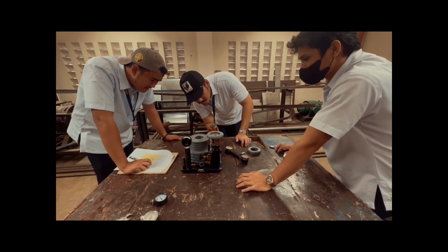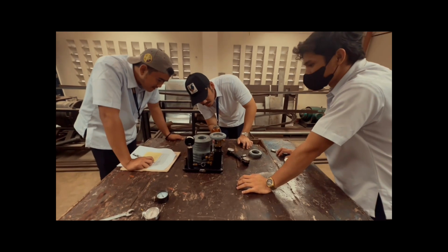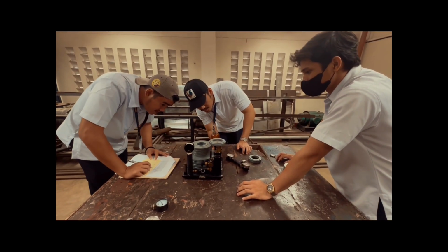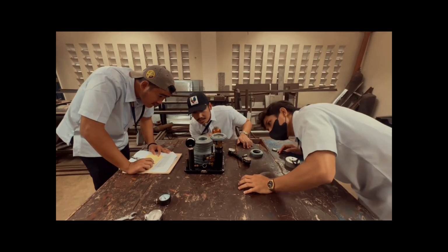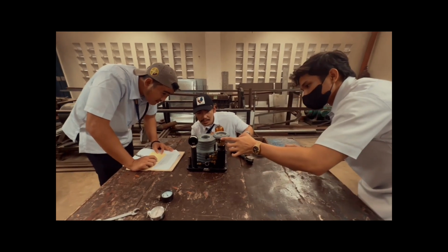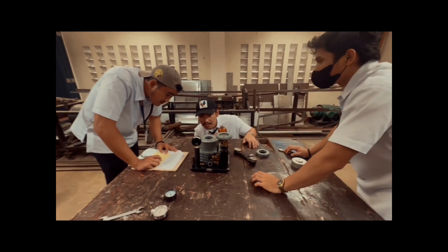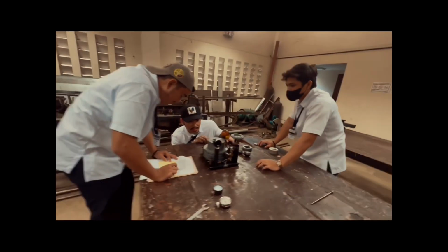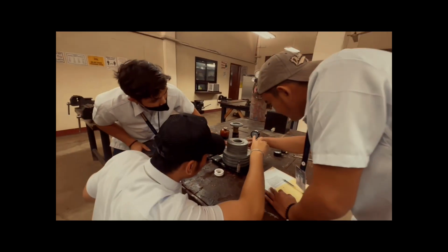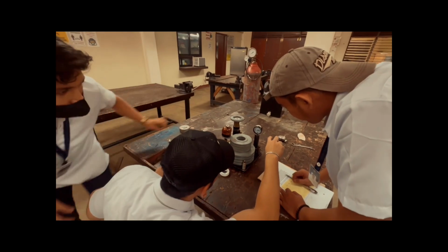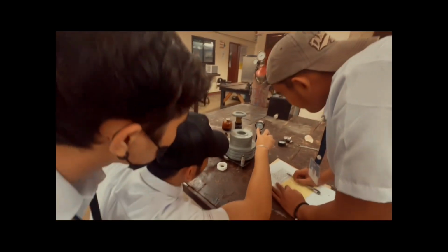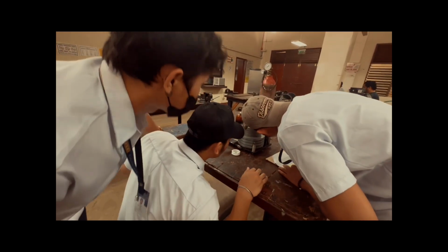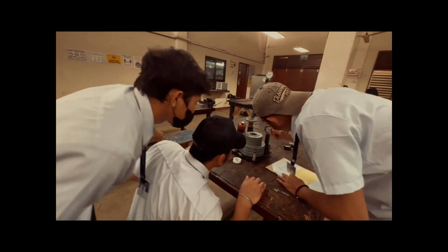For the steps and procedure, first is to ensure that the testing area is clean, dry, and well lit. Second is to place the dead weight tester on a stable surface. Next is to verify that all necessary adapters and connectors are in place for the specific pressure gauge being calibrated. And lastly, check that the dead weight tester and pressure gauge are at room temperature.